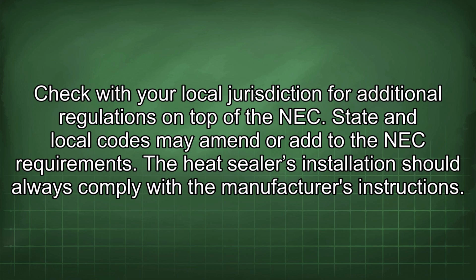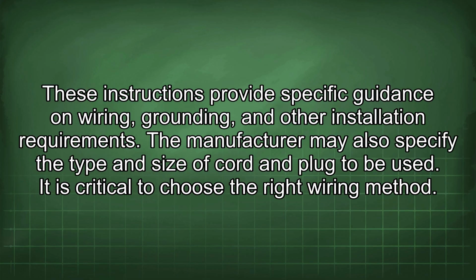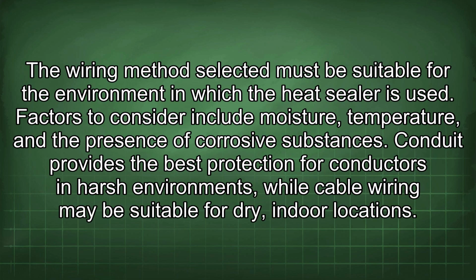The heat sealer's installation should always comply with the manufacturer's instructions. These instructions provide specific guidance on wiring, grounding, and other installation requirements. The manufacturer may also specify the type and size of cord and plug to be used. It is critical to choose the right wiring method. The wiring method selected must be suitable for the environment in which the heat sealer is used. Factors to consider include moisture, temperature, and the presence of corrosive substances.